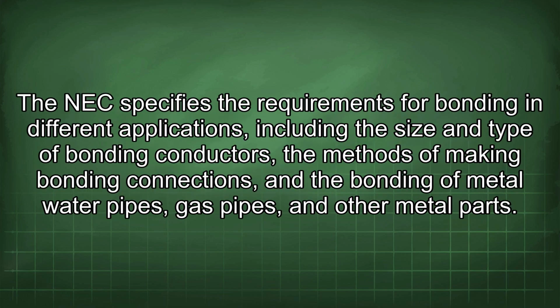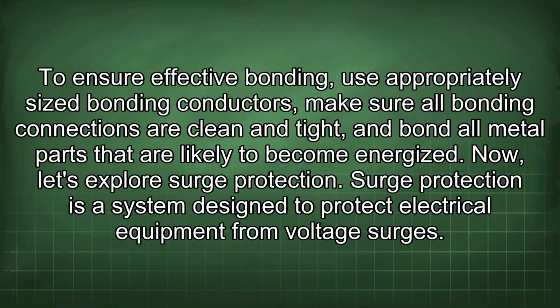The NEC specifies the requirements for bonding in different applications, including the size and type of bonding conductors, the methods of making bonding connections, and the bonding of metal water pipes, gas pipes, and other metal parts. To ensure effective bonding, use appropriately sized bonding conductors, make sure all bonding connections are clean and tight, and bond all metal parts that are likely to become energized.